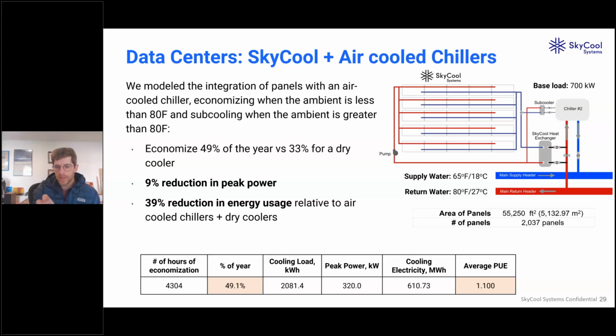What we're presenting is using the panels to replace the dry coolers in the system. Essentially, the panels are able to provide direct chilled water in the winter or shoulder seasons, so fall and spring. And then when it's hotter outside, we're subcooling the chiller to provide efficiency. So we ran essentially an 8760 model. This is for a site in North Carolina.